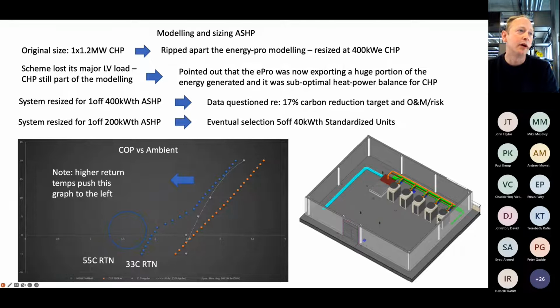A complete side note here, but the higher the return temperatures that you get from your network or building, the more this shifts to the left, and not an insignificant amount either. So I've just sketched on there. I should have made that blue line slightly thicker, but you see how the coefficient of performance drops very significantly when you start running to buildings that are running on high temperatures. I'm sure a lot of you already know that.